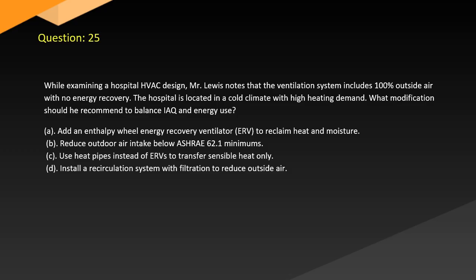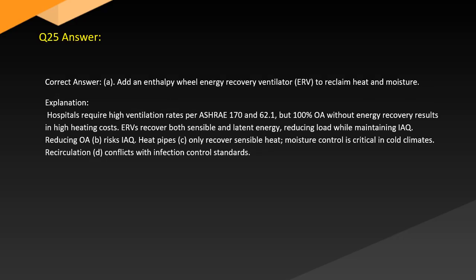A. Add an enthalpy wheel energy recovery ventilator to reclaim heat and moisture. B. Reduce outdoor air intake below ASHRAE 62.1 minimums. C. Use heat pipes instead of ERVs to transfer sensible heat only. D. Install a recirculation system with filtration to reduce outside air. Answer. Correct answer A. Add an enthalpy wheel energy recovery ventilator to reclaim heat and moisture.